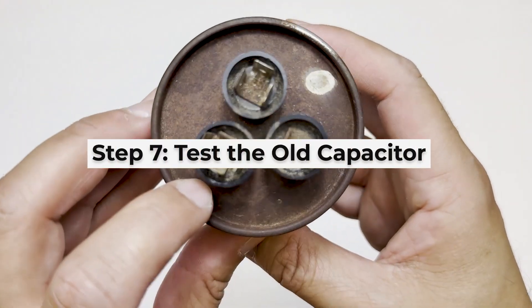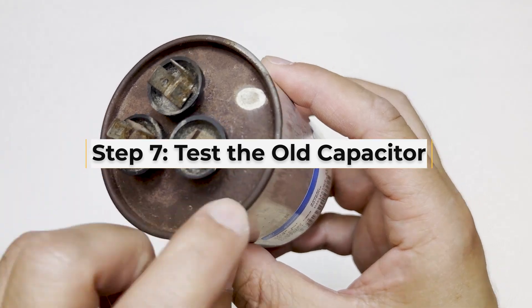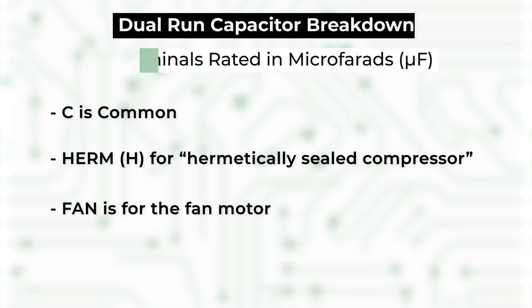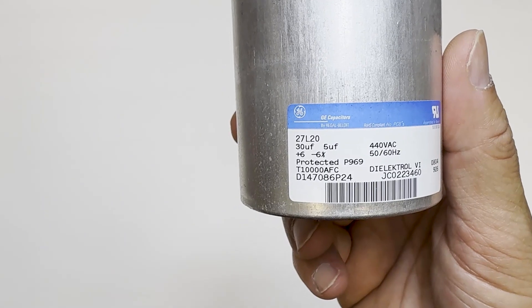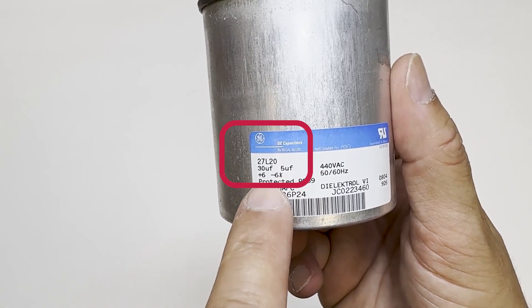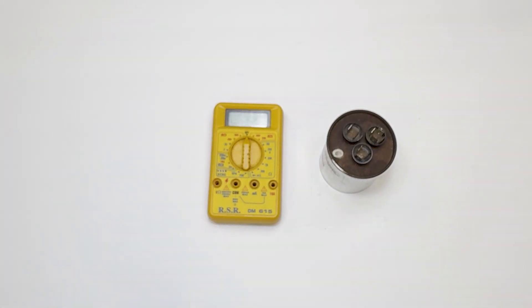Step 7: Test the old capacitor. You can see our capacitor is bad. It's domed and bubbled up, but we'll test it with a multimeter anyway. The capacitor has three terminals. C is for common, herm for hermetic compressor, and fan. Looking at the labels of the capacitor, confirming again that it is 30 by 5 microfarads with plus or minus 6%. We will test it with a basic multimeter and another multimeter that has the capacitance function.